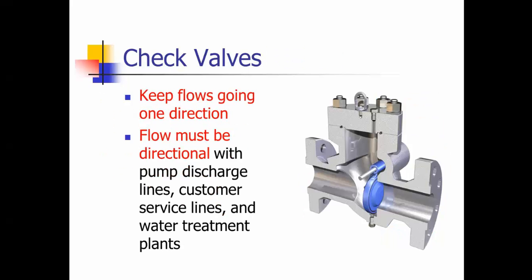This is a check valve, and what they do is they keep the flow directional. As the water hits this paddle, it moves up and the water passes through it. So when the flow stops, it backs up, and this slams shut. You get more water hammer with these types of valves. The flow needs to be directional with the pump discharge lines, customer service lines, and water treatment. If you start a pump up, you want to make sure that the fluctuating pressures in the line caused by a check valve level out before you start the pump back up because of the water hammer.